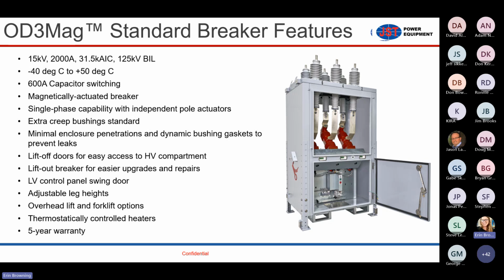But I also want to point out the high voltage cabinet door is not pictured here because it's a lift off door. You're able to lift it off and remove it easily. It's a lightweight door made out of aluminum with handles, and I'll show you that on another slide. The low voltage panel is a swing door. We can put this on either side of the breaker, left or right, with a 3-point latching system for the handle.